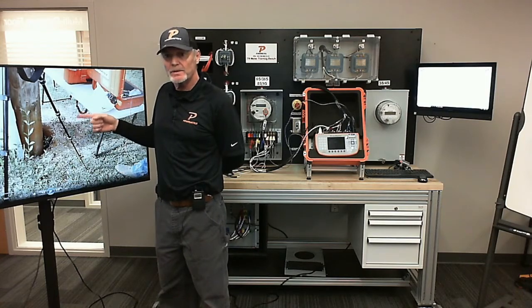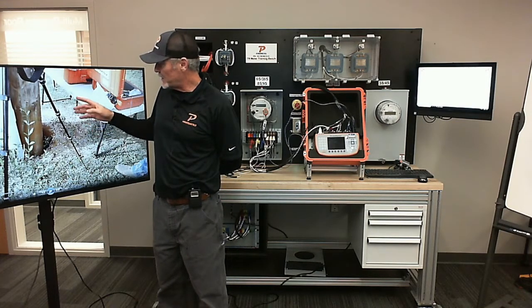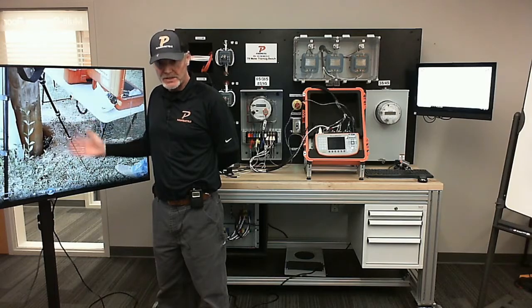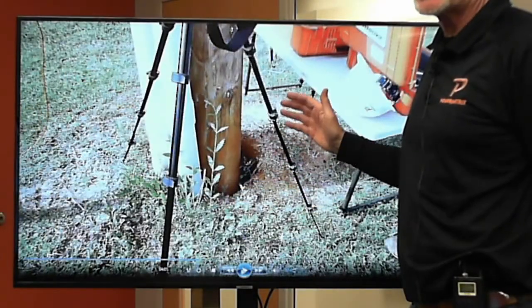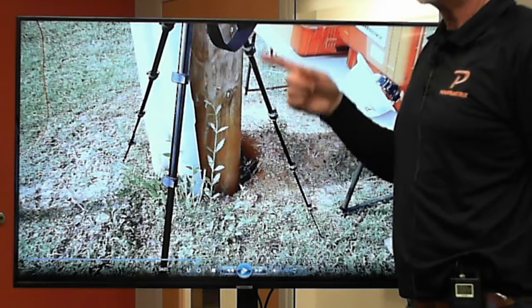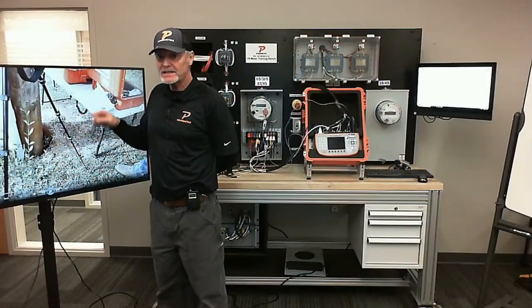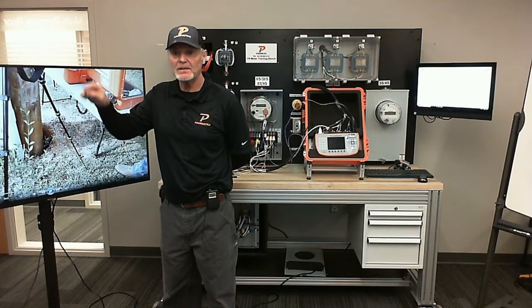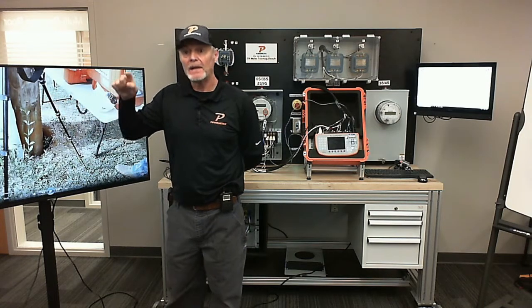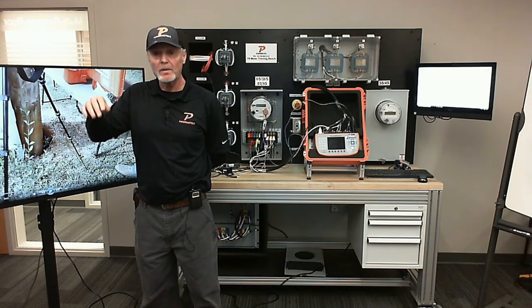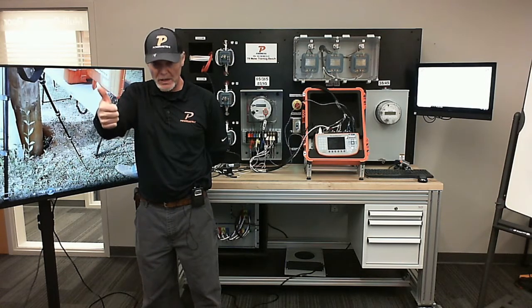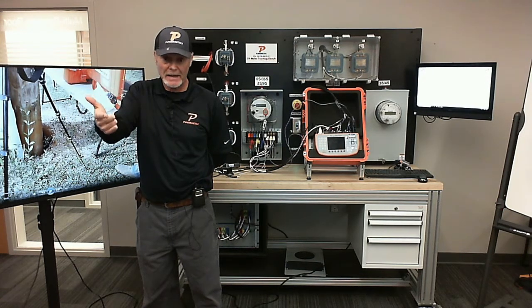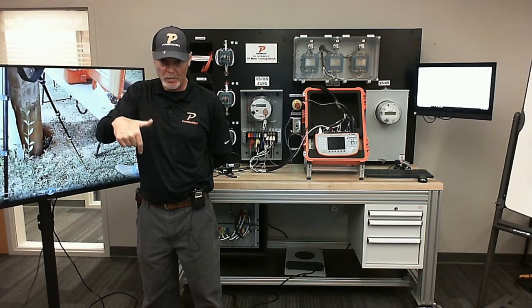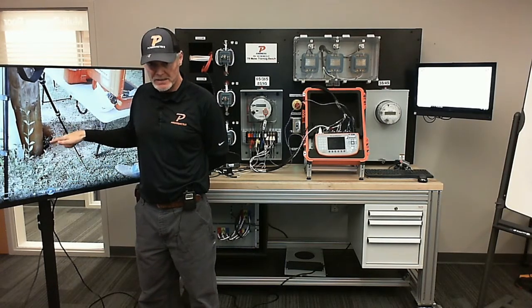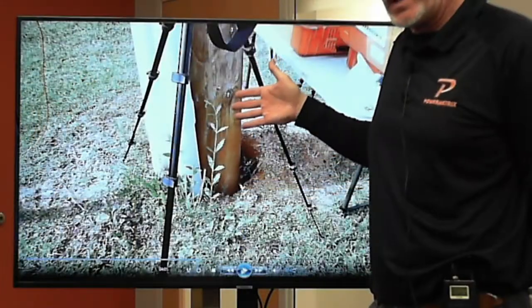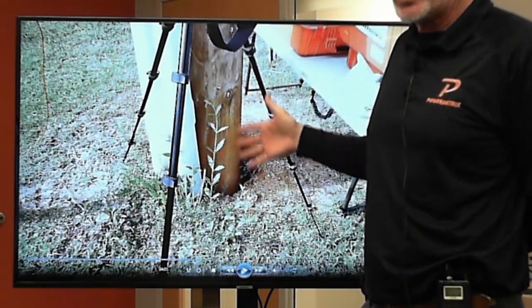That's something you would definitely want to report back, because as I said, these don't get any better. Once it starts that washout process, it just keeps washing out. Remember, you as the meter techs are the eyes and ears of the utility on a continuous basis at these sites. The linemen, unless they have a dual role, usually only show up for new construction or if there's a problem out there, and they're depending on you to report it. This would be one you definitely want to let somebody know about, because it's not that old of an installation.